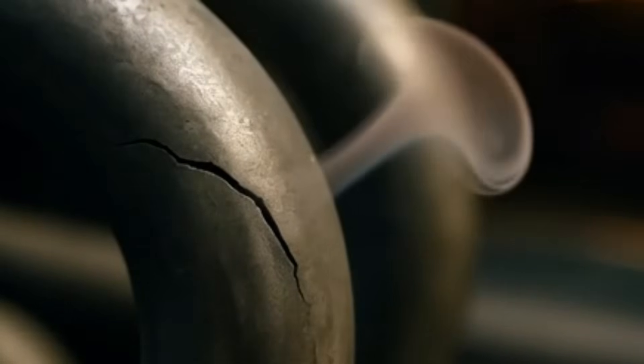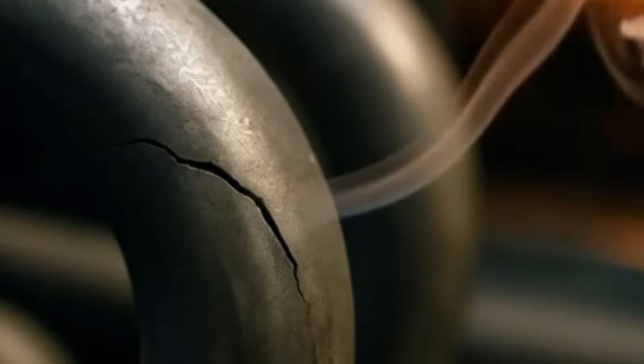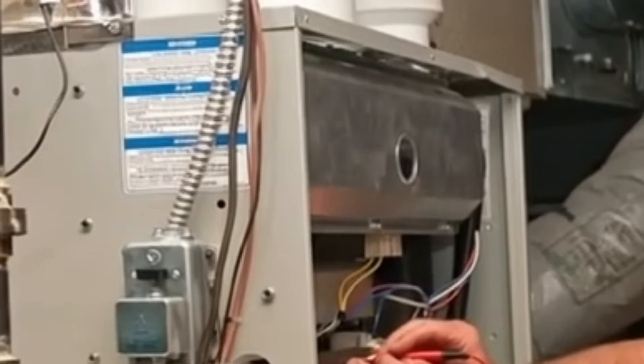The best part is timing. I mentioned at the beginning how pressure switch problems can give you clues on heat exchanger problems. In one situation, the furnace had a sealed combustion chamber, and the furnace fired up just fine — but as soon as the blower motor came on, the whole thing shut down.